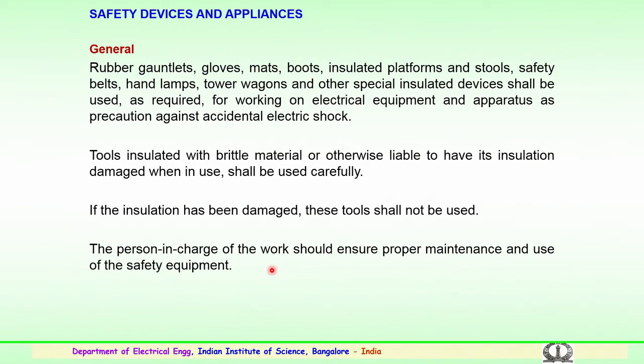So, these gauntlets or insulating mats, the insulating shoes and the insulated platforms are used for safety. Apart from this, proper safety belts are used in case of personnel operating at a higher level, along with suitable lamps, hand lamps, which are used for the maintenance. There could also be tower wagons and other specially insulated devices used whenever required for maintenance or working on the electrical equipment and apparatus, as a precaution against accidental electrical shock. So, several of these devices or appliances are being used.